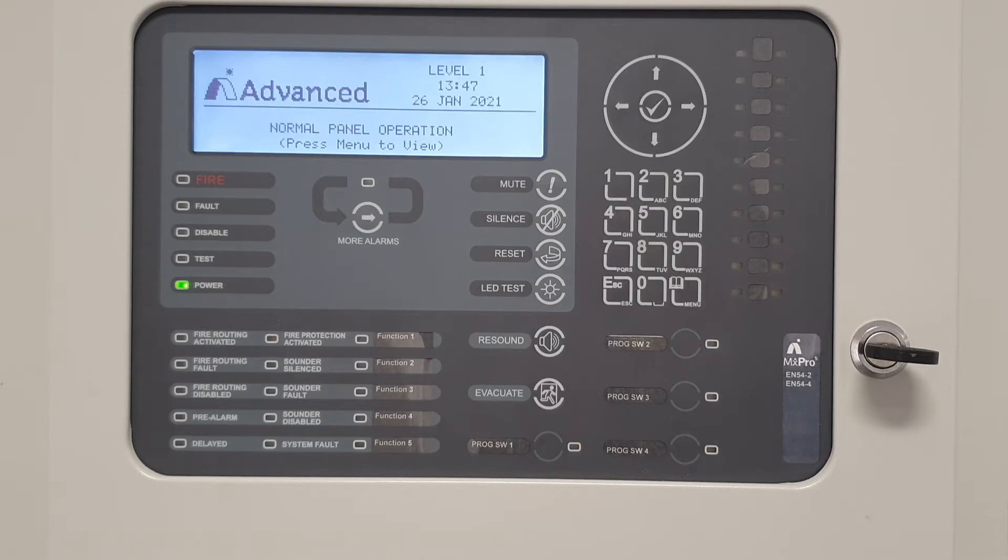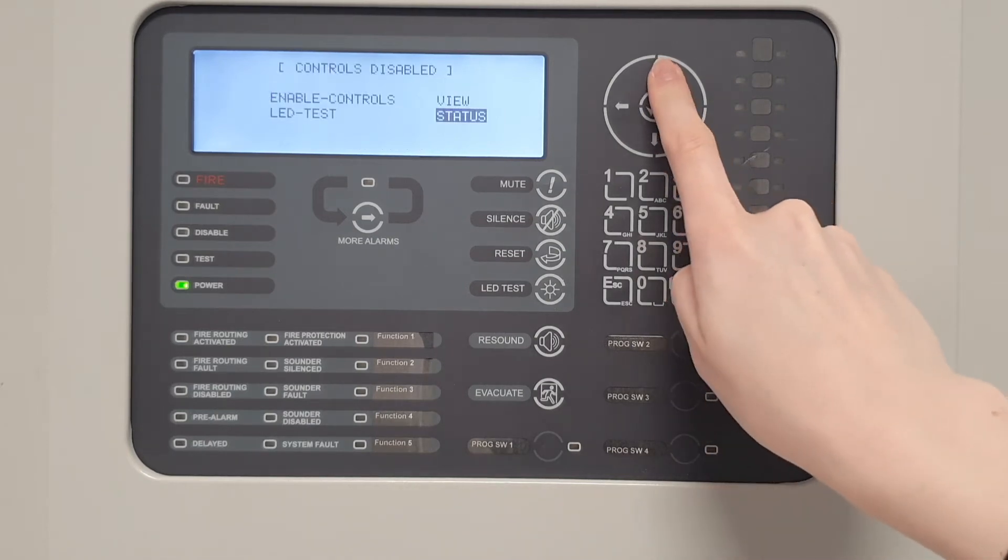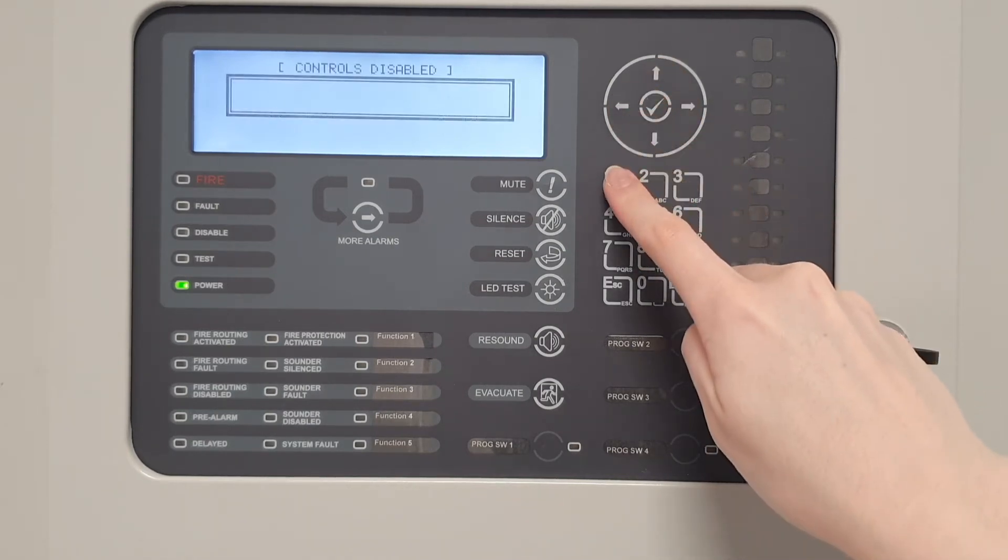Once the zone or device has been disabled, the disabled LED will show on the panel display. Devices cannot be disabled when the panel is in Access Level 1, and therefore the password must be entered to get into Access Level 2. By default, this code will either be 10,000 or 10,001.